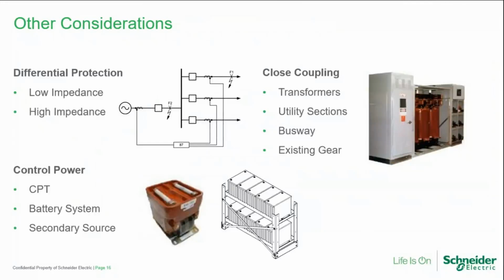Other things to consider: differential protection. With newer styles of design, it's more difficult to do differential protection due to limitations on types and amounts of CTs that fit into the switchgear. But with GIS and SIS, one of the main points is to help prevent phase-to-phase crossover with these more modern insulating systems. So the question really is, do you need bus differential protection with these newer styles of switchgear? At the end of the day, that's up to you as the designer. But then the question is, could I use a low impedance bus differential system as opposed to a high impedance one, and be able to share some of the CTs between normal protection and bus differential protection?